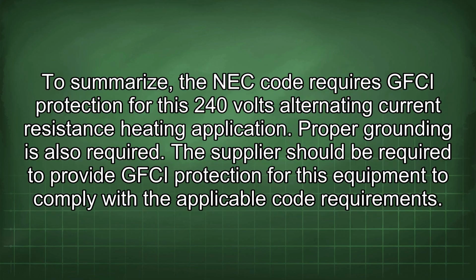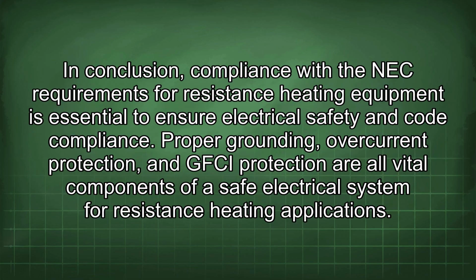To summarize, the NEC code requires GFCI protection for this 240 volts alternating current resistance heating application. Proper grounding is also required. The supplier should be required to provide GFCI protection for this equipment to comply with the applicable code requirements. In conclusion, compliance with the NEC requirements for resistance heating equipment is essential to ensure electrical safety and code compliance. Proper grounding, overcurrent protection, and GFCI protection are all vital components of a safe electrical system for resistance heating applications.